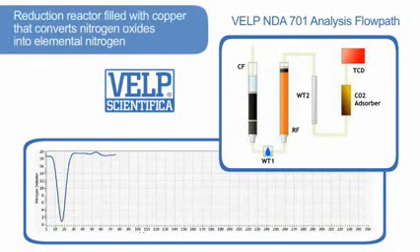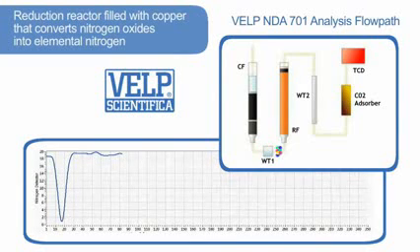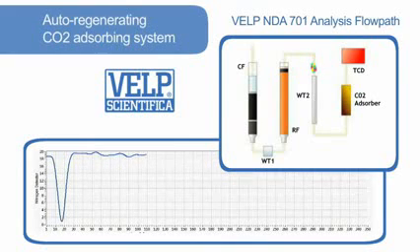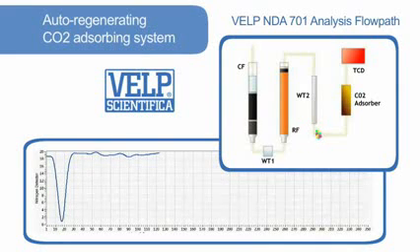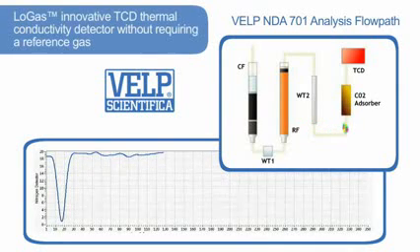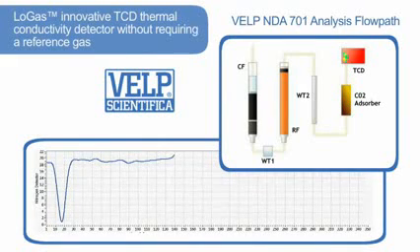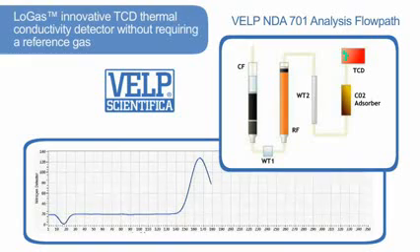The gases pass through the reduction reactor, filled with copper, that converts nitrogen oxides into elemental nitrogen at 650 degrees centigrade. Any remaining water is completely absorbed by the second chemical water trap. A maintenance-free auto-regenerating CO2 adsorbing system ensures the elimination of all CO2. At the end, the remaining elemental nitrogen is detected by the innovative LoGas TCD thermal conductivity detector, without requiring a reference gas.